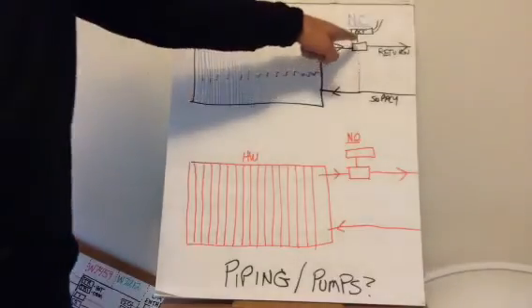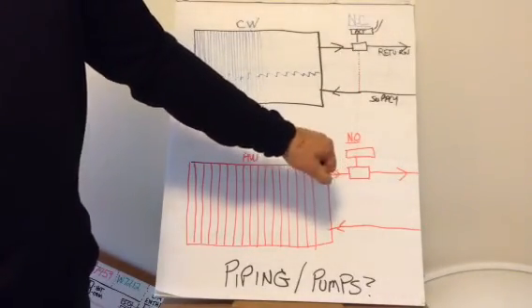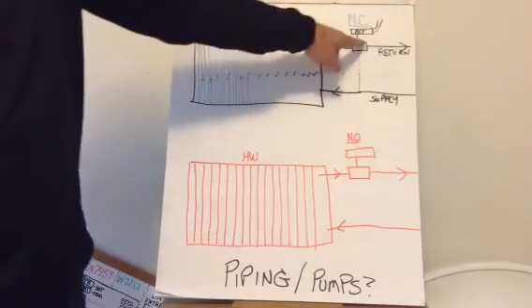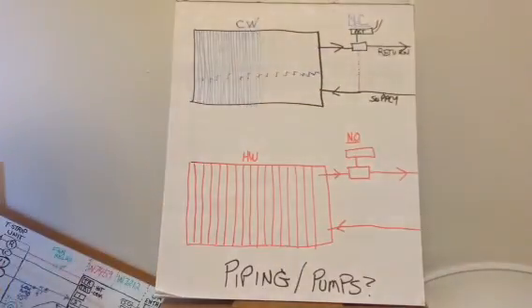Quickly while I'm here, most malls nowadays have a 3-way valve instead of a 2-way valve. They do that so that there's always water going back to the plant, the cooling plant or the chilled water plant. You need to pay attention to that because that changes the logic of the unit. The other thing I wanted to note while I'm here is you'll notice that on the hot water coil, that doesn't say no, that says NO for normally open. If it's set up properly, guys, if you have a 4-pipe system, the hot water coil, the actuator and the valve for it, these should both be spring return actuators.